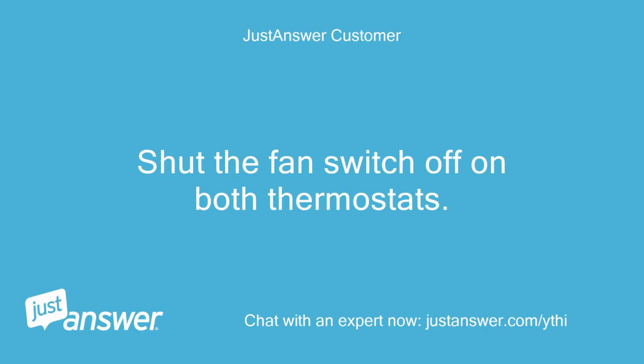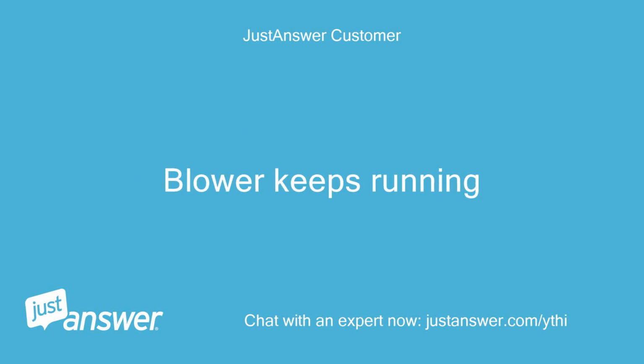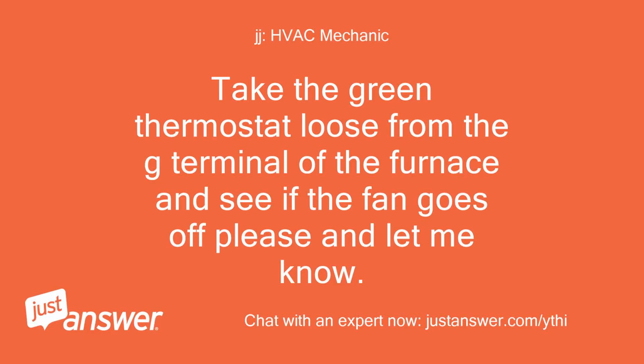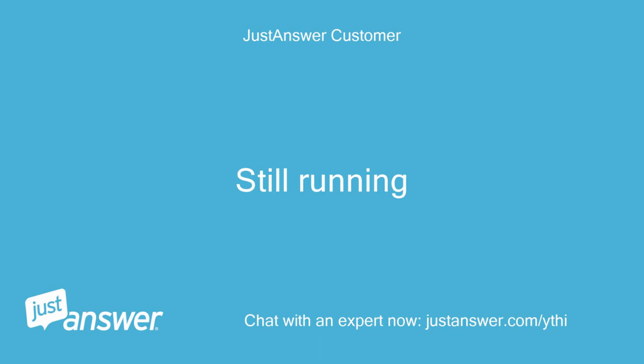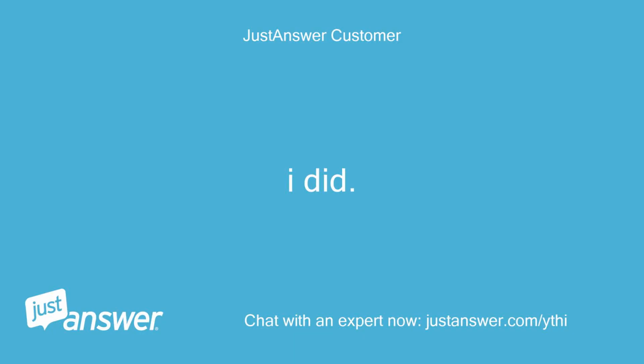Shut the fan switch off on both thermostats. Turn temp down so that thermostat temp has been met. Blower keeps running. Take the green thermostat wire loose from the G terminal of the furnace and see if the fan goes off, please, and let me know. Still running. Reset the main power and it should go off. I did. It kept running.